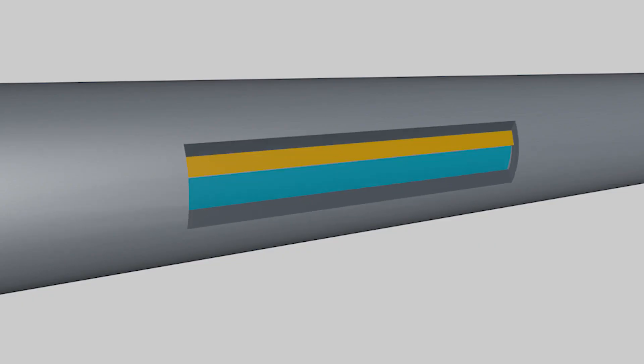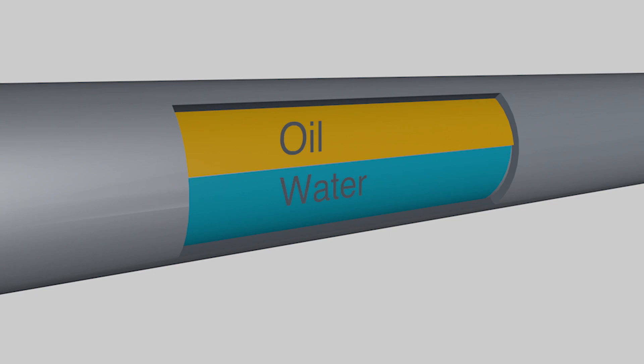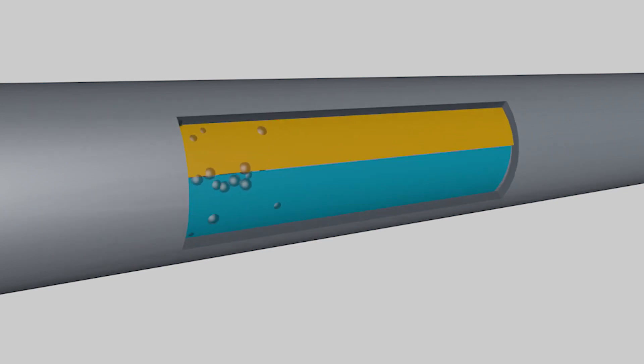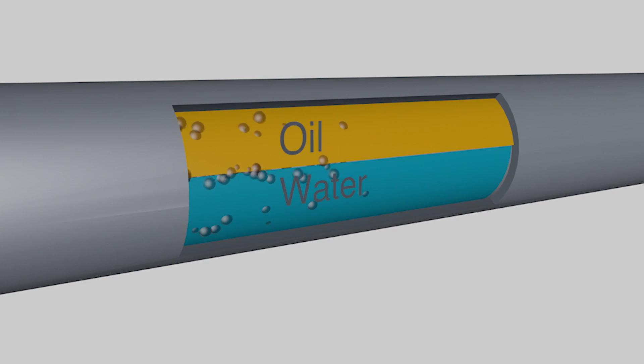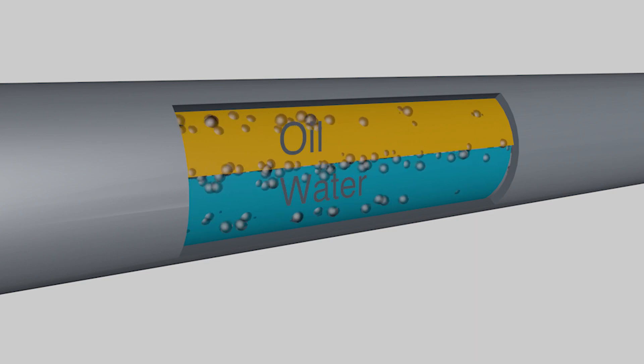The measurement of net oil and water cut by a Coriolis flow meter would be very straightforward, accurate, and reliable if only two-phase liquid existed — that is, oil and water. However, in many practical applications, it is very common to have entrained gas in the oil-water emulsion.